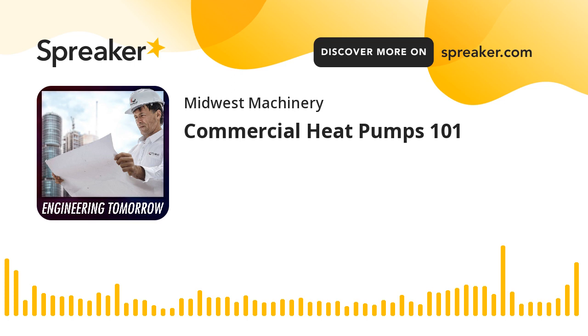Specifically, water source heat pumps, the advantage that you have there is you're pumping water around your building and not refrigerant. So what the water source heat pump manufacturers will tell you is water source heat pumps are better because you're not having a safety issue with refrigerant lines in your walls, that if someone drills a hole in the wall, punctures a refrigerant line, springs a leak, that could be potentially dangerous. Not to mention you would have a very hard time finding that leak to where you could repair your system.